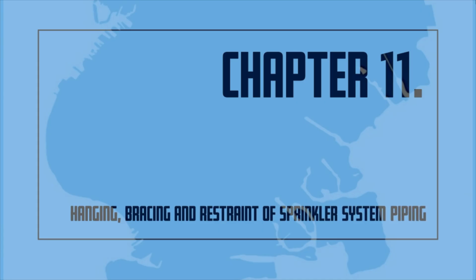Piping shall be supported from the building structure in accordance with the New York City Code requirements and National Fire Protection Association No. 13, 2002 edition. The annual visual inspection of system hanging components and bracing is the most complicated and difficult of all the tasks to be performed by the certificate of fitness holder. This reference is a starting point, and by no means does it fully explain the various means, methods, and requirements to adequately perform this annual inspection task.